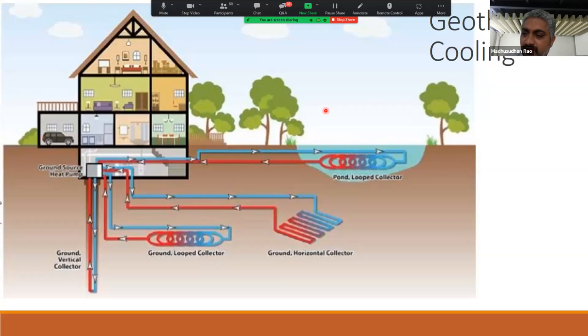Lastly, though in theory Earth is an infinite sink, it cannot take continuous dumping of heat. In India, most places have only cooling requirement, whereas in the West, it is both heating and cooling. So what happens in the West is that in one season you dump the heat. In summer, you go on dumping the heat and that heat accumulates and increases the temperature of the surface soil. By the time summer is over and winter comes, you're extracting the same heat. You get better performance again in winter because you are trying to get heat from the ground. So the cycling of the soil happens and energy balance is maintained. And therefore, these bores can be used for longer periods.